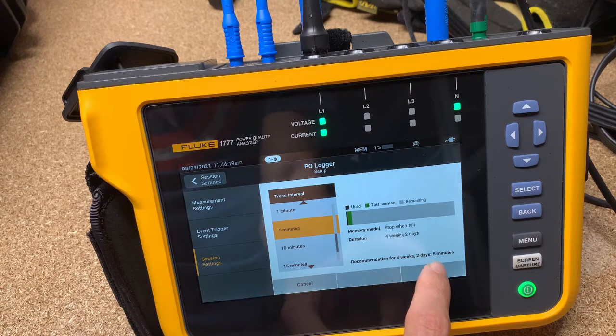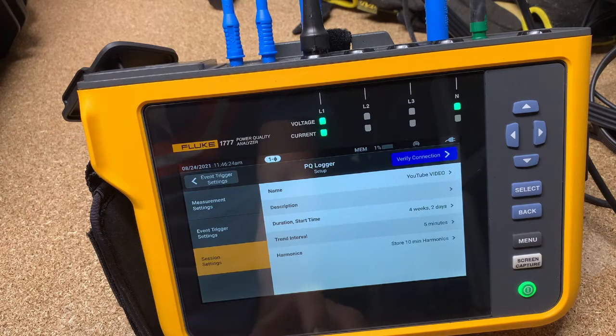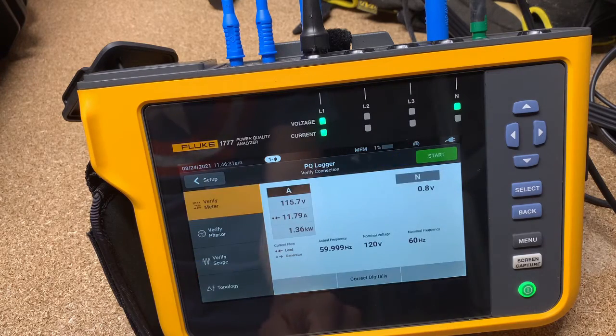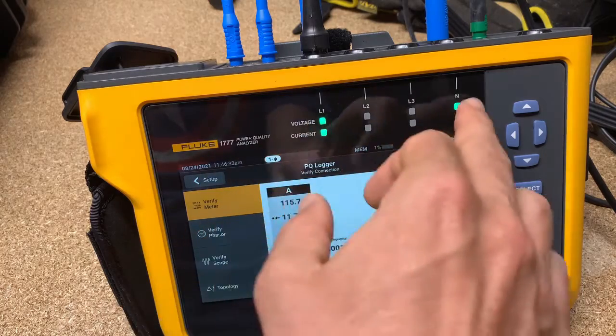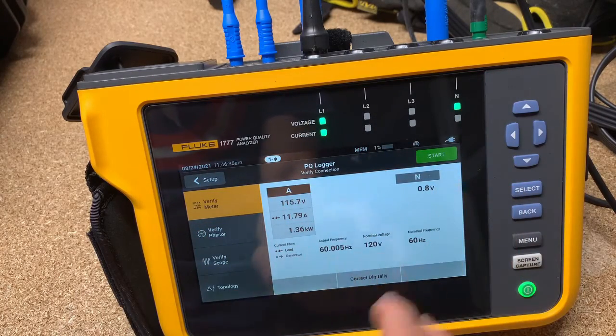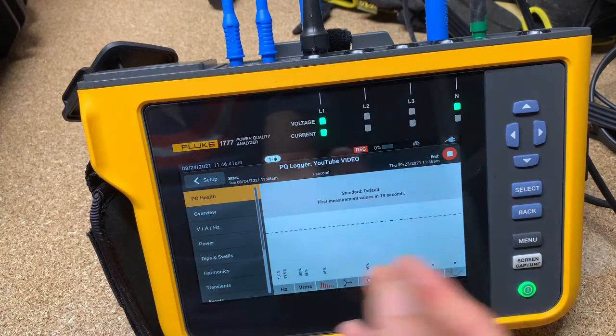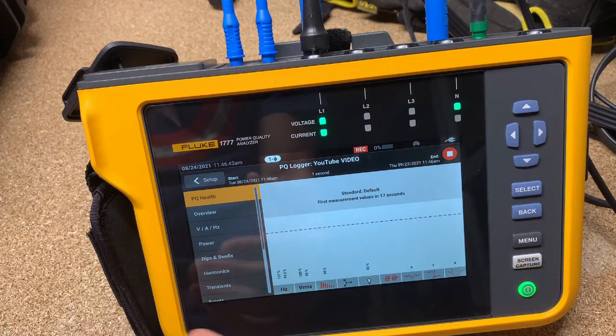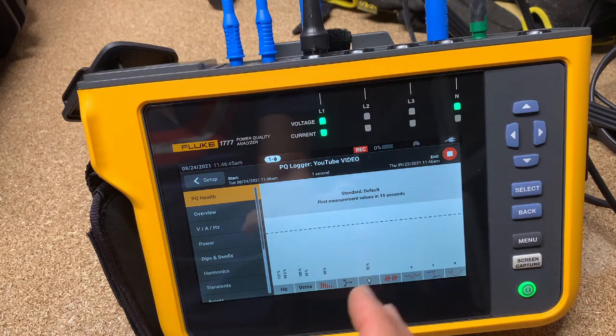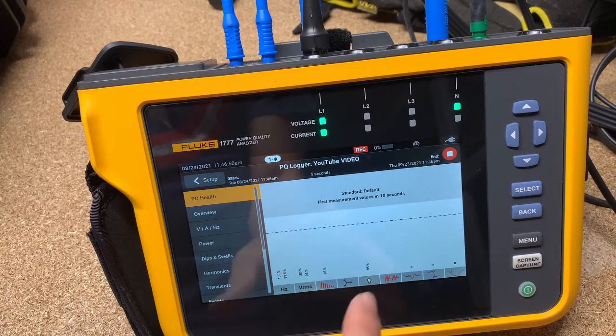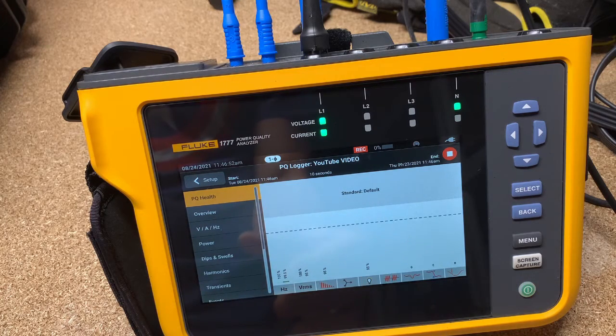It says for a four-week, two-day study, five minutes is recommended, so that's what I'm going to go with. And then harmonics — you can see that. Once you do all those things, it's going to ask you to verify your connection. And because all of our lights are green and it's happy and nothing seems to be upset, we can hit start log. It will then log for a period of time. Because it is a five-minute interval, I'm going to let it log for a little bit, and then I'm going to come back and show you how we're going to get the data off of this.